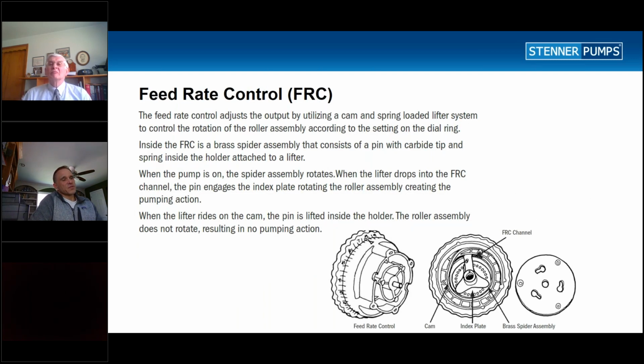So the feed rate control is going to adjust the flow rate of the pump based off the tube that's inside or on the pump itself with the gearing. And what's going to happen is that when you look at it on the back there, that spider is rising and falling. So every time that spider is seated down on the index plate, it's moving the index plate, which is then moving the shaft and then moving the rollers, moving fluid through the pump. The cam that you see pointed on there, that's that white plastic piece. Some people call it a weed whacker. I kind of think of that as almost like a bypass. So what's going to happen is that index plate's going to rise up onto that cam, and in that position, the pump is not pumping and not moving fluid through the pump.